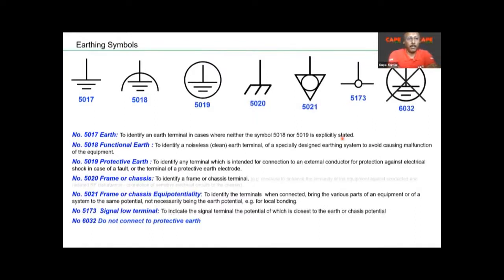For this purpose, the IEC and all the world standards define earthing into various types, and various numbers are allocated to each earthing. This is followed not only by IEC, it is the same in ISO, ITU, and all the standards. For example, 5017 is a generic symbol. 5018 is an earthing which is called a clean earth, or the new word, functional earth. For functioning of an electronic appliance, the appliance, the panel board, or the PLC will have an earth terminal which is marked with 5018.